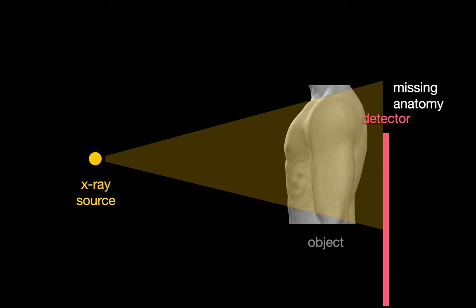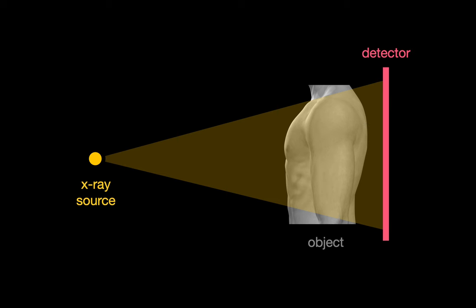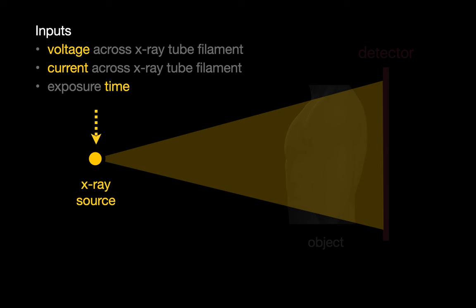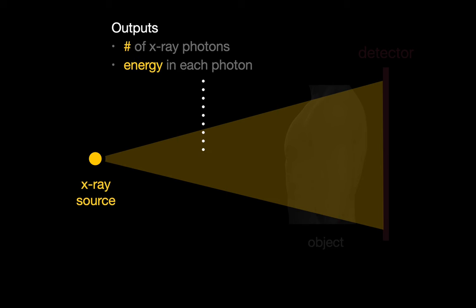If the x-ray beam is not angled but shifted too high or too low, then a portion of the patient's anatomy may be excluded from the chest x-ray. Obviously, the same thing applies if the film or x-ray detector panel is shifted too high or too low too. Besides position, we can control the voltage and current across the x-ray tube's filament in addition to the exposure time of our image. These variables allow us to manipulate the total number of x-ray photons we fire at the patient's chest and the amount of energy each individual x-ray photon packs.